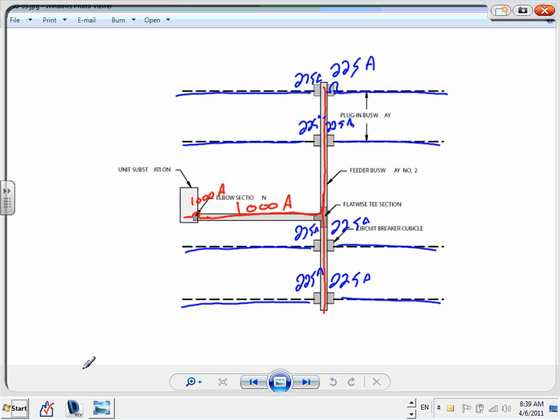In our case, the plug-in is going to be 225 amps, and the bus will also be 225 amps. And Jim, the overcurrent protection device: can you see it? Each one of them is going to have an overcurrent protection device. What do you think it's going to be? 225. So regardless of your calculation, Spencer, please use 225 amp as your minimum on the plug-ins in our building. And the feeder is going to be based on my calculation.